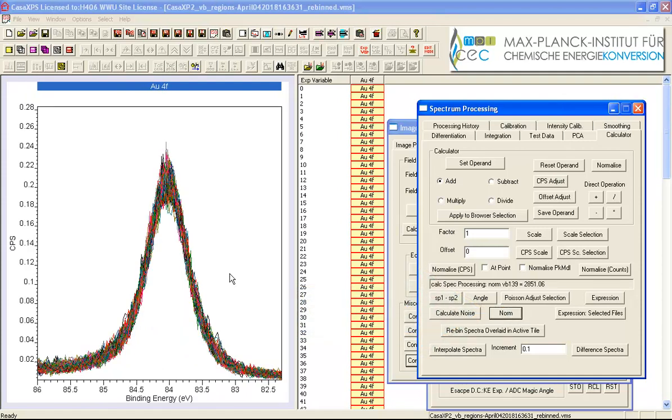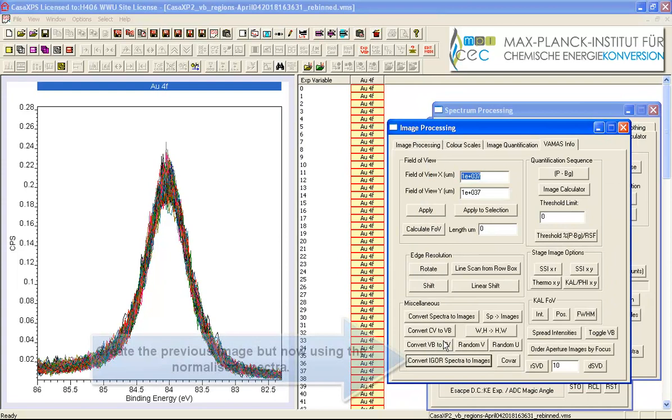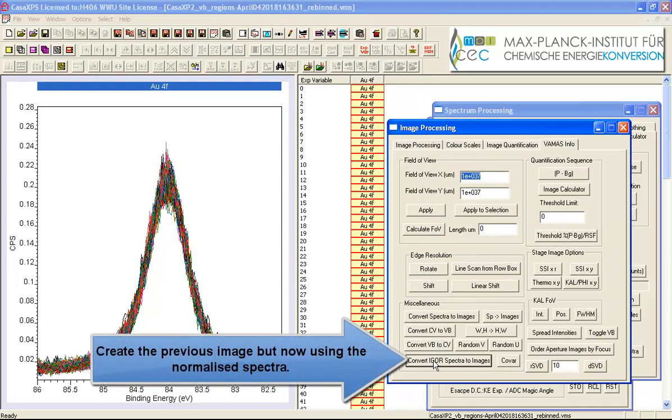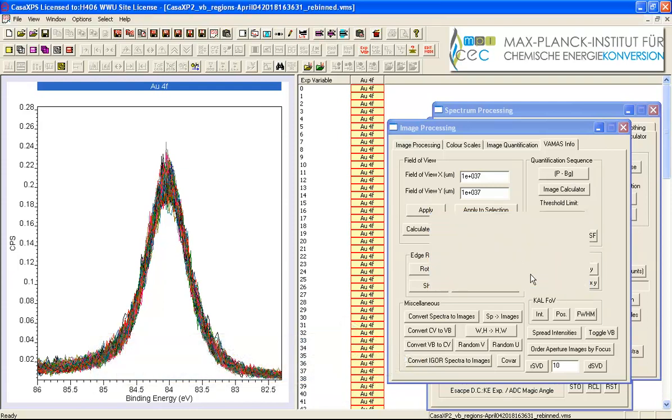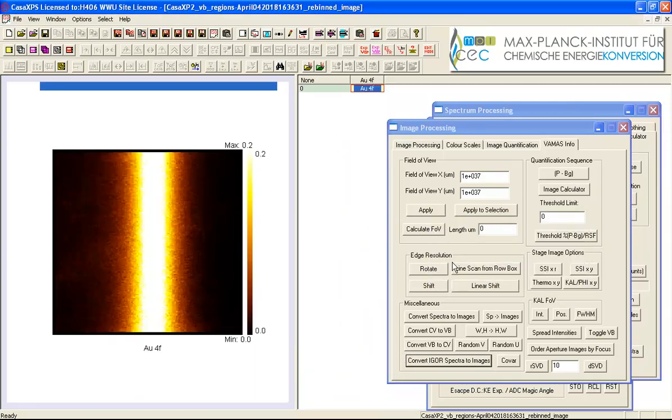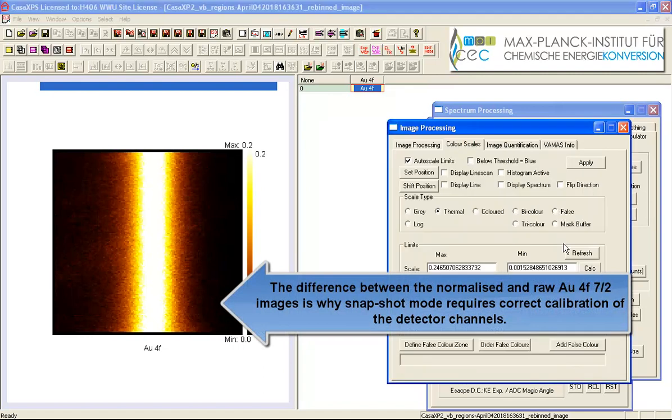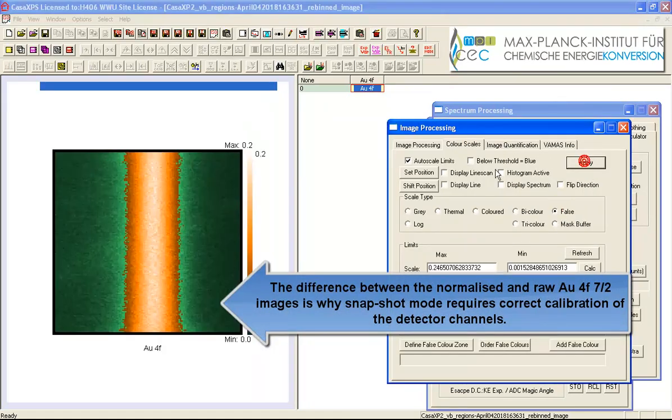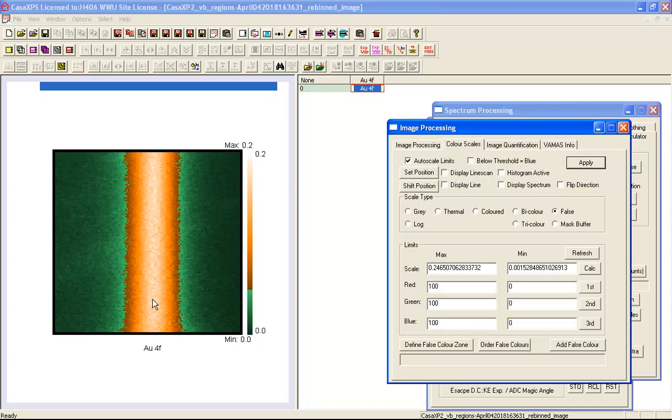So if I normalize these peaks, this is not something you do before summing, this is simply so you can do a check on your spectra, make sure the peaks are similar. And if I look at the image again that's what you would ideally like to see, a perfectly vertical line in this image. Let's just give it a bit more definition. So that would make you feel very comfortable that you could add these together without introducing too much of an artifact assuming that you've been through this calibration procedure as I've just performed.